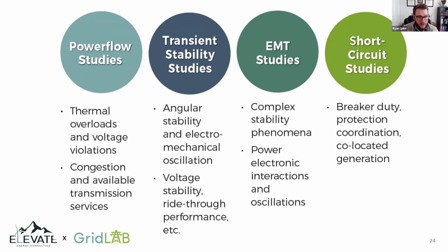And then you get into the stability, the classical positive sequence transient stability study. Here we're looking for - I'm adding in large loads and I'm looking for, do I have nearby synchronous generators going unstable? Have I created any electromechanical oscillations, the natural modes of the system? Do I have voltage stability problems, voltage collapse issues, ride-through performance issues of nearby elements or even for the large loads themselves? Those types of studies are necessary to look for more of the stability implications.